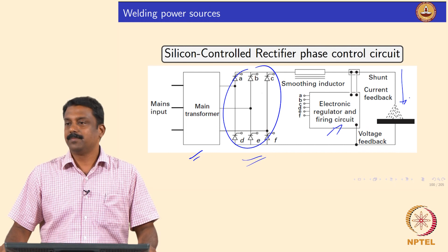Unfortunately, in our case we also need a low voltage, high current arc. So we need to define the circuit, and the efficiency is determined by the components you have. Compared to the moving iron power source, the SCR phase control power source is much more efficient, because the heat loss is lower by using SCRs in the circuit. We also use all three phases coming from the mains to regulate the outputs. It is nothing strange, it is the same as what you have in computers. So this is clear, the SCR phase control circuit.